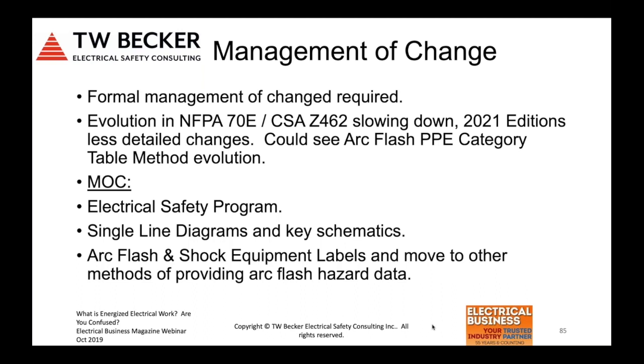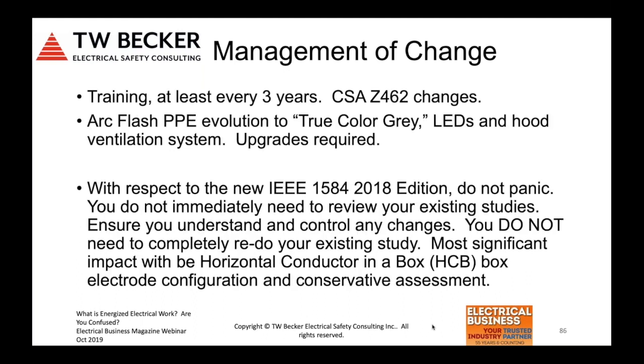Arc flash and shock equipment labels, if you do change your labels, they need to be MOC'd, right? And I encourage you to look at the labels you've installed and make sure they're compliant labels. Training, at least every 3 years, aligned with the Z462 changes. So you do have to manage that change, and training should be approved when the standards change. Arc flash PPE evolution to the true color gray lens, LEDs, hood ventilation system upgrades required, right? So there's two concepts here I'm communicating with management of change. You should evolve with change, plus we want to make sure that we have specific approvals of some of these changes as well. The last point on this slide is the IEEE 1584 2018 edition.